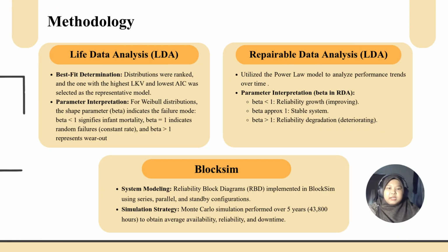Moving into our technical methodology, we utilize two primary software environments for this RAM study, which is Weibull++ and BlockSim. Our process begins with life data analysis or LDA. We imported historical failure data into Weibull++ to identify the best fit distribution for each equipment group. Using the likelihood value and AIC as our primary ranking criteria, the shape parameter or beta was crucial here. It told us whether a component was in its infant mortality phase or failing randomly or entering a wear out stage.